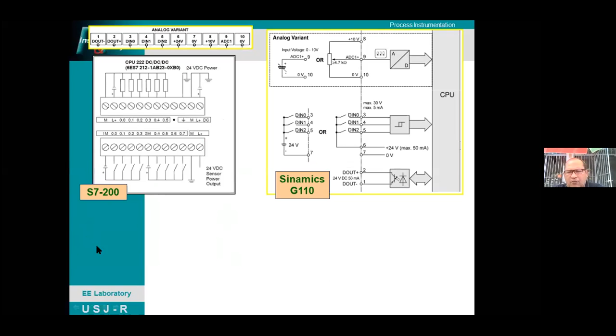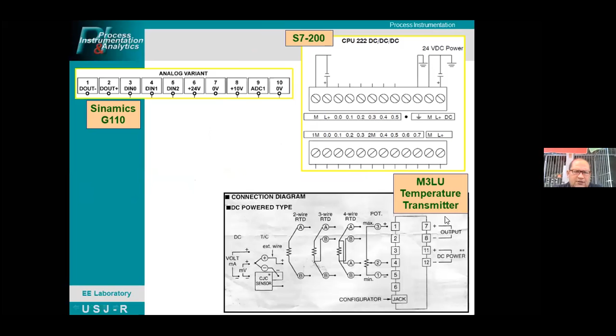Then for the analog variant, for the Sinamics G110, the S7-200, then the temperature transmitters. Set the system up so that the PLC is the command source and the temperature transmitter is the frequency set point source of the inverter. Showing the wiring between control devices and parameter configuration, where a type K thermocouple will be used on the transmitter.